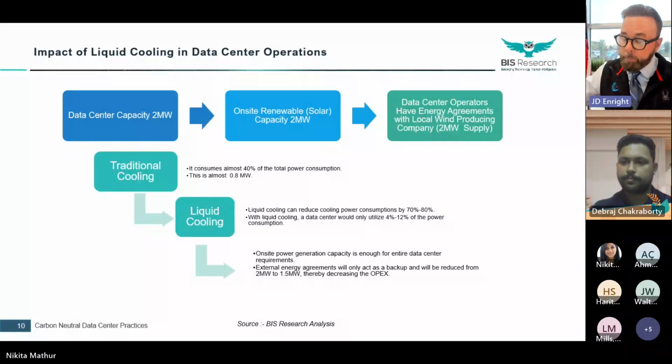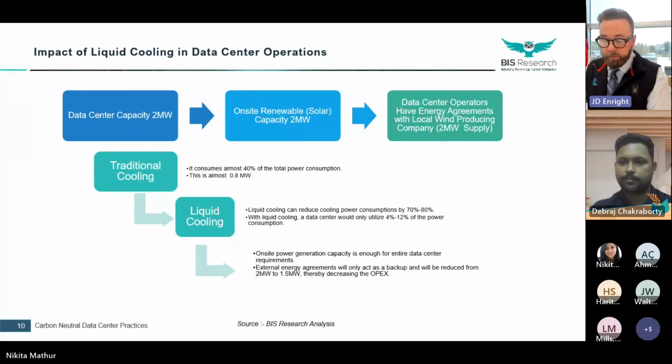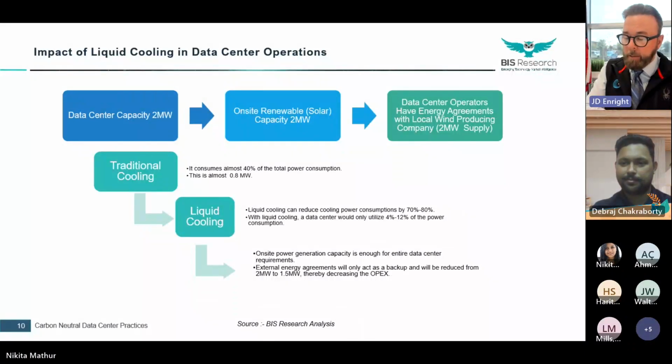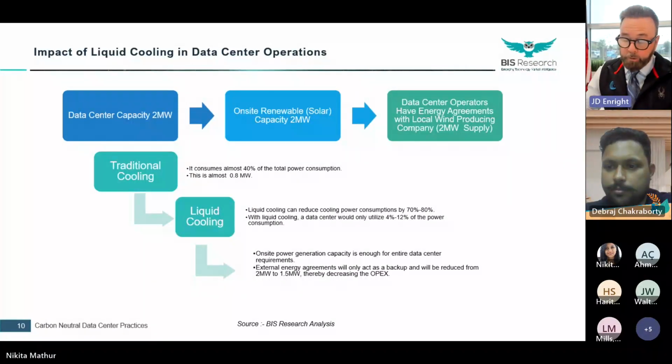You never have to replace it, and you can repurpose it and filter it. We have a filtering process. If something were to happen and it got contaminated from dirt or whatever, even servers come right off the production line with solder flux and hair from the production. It's amazing what we've seen and filtered out from brand new servers right out of the box. So having processes for cleaning this out, we use filtration processes, which are very low cost and very low carbon, not carbon neutral, but very low carbon. They're actually carbon filters, and they last for a very, very long time. So keeping the fluid hygiene is key.